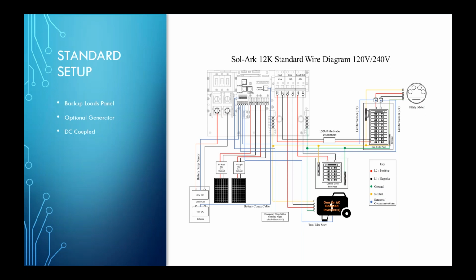So this is a wiring diagram. This is a standard wiring diagram. It's just kind of a very basic setup. It does include batteries. It does include solar. It does include a generator. It does have a critical loads panel, and it does have the CTs. Dustin, you may want to walk us through this real quick, just kind of give us an overview of the wiring diagram. Absolutely. So this is a very standard 120/240 kind of setup.